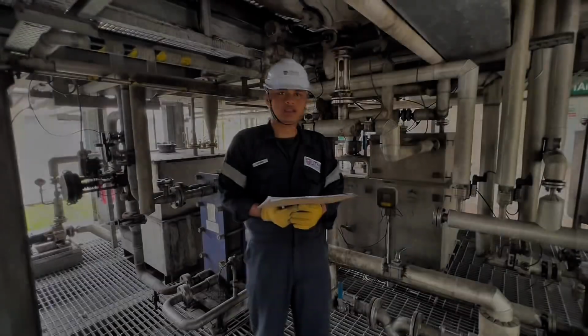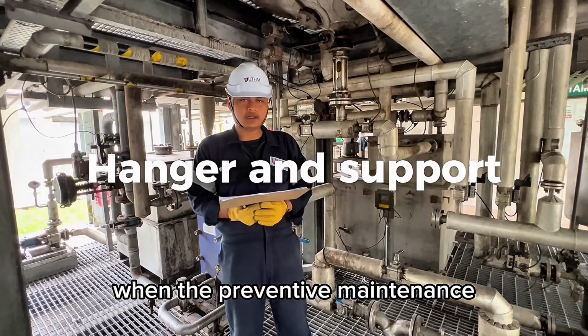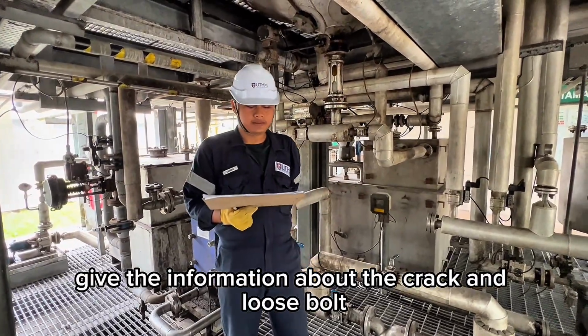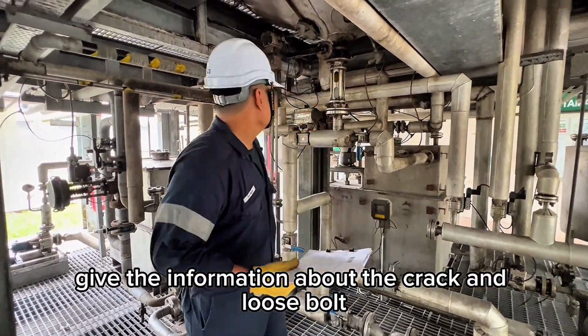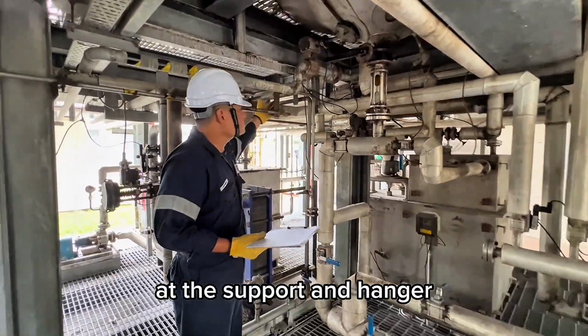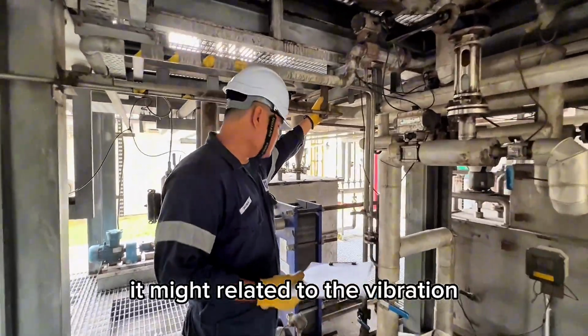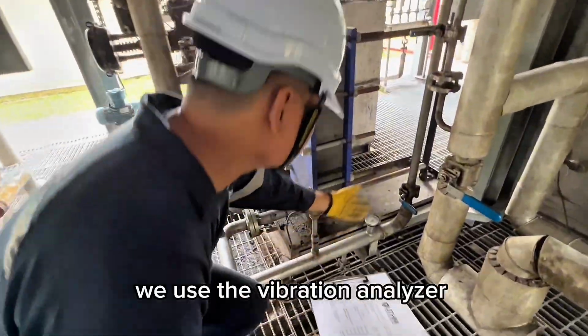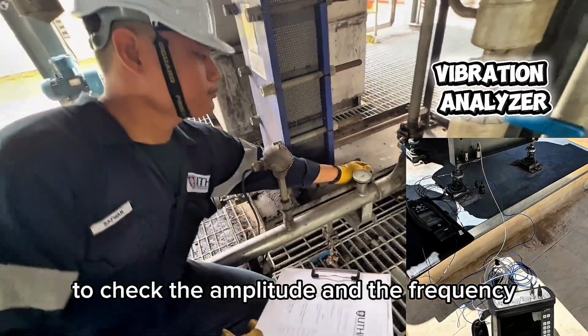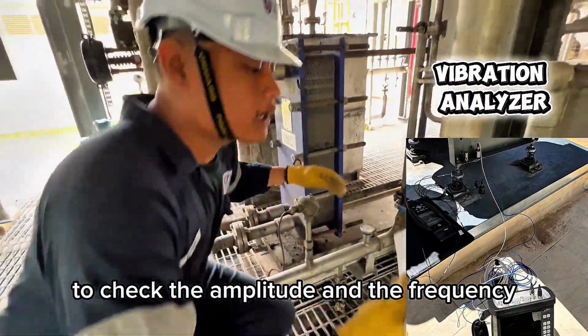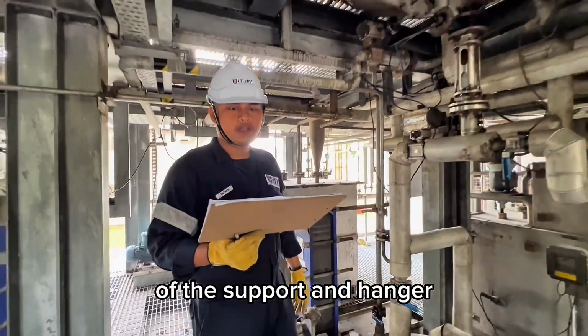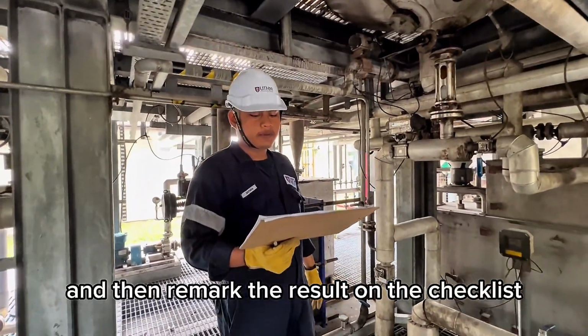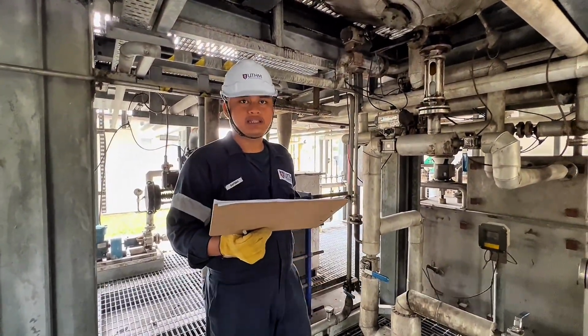When the preventive maintenance gives the information about a crack and loose bolt at the support and hanger, it might be related to vibration. Here, we use a vibration analyzer to check the amplitude and the frequency of the support and hanger, and then remark the result on the checklist.